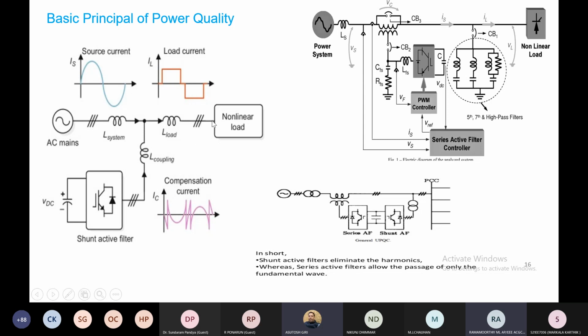Basically, all the components demanded apart from the fundamental are supplied from this side. That means if we have 1, 3, 5 components - 1 meaning fundamental, 3 meaning third harmonic, 5 meaning fifth harmonic - if 1 plus 3 plus 5 is supplied from the generator, after connection of this active filter, third and fifth will be supplied from here instead. The generator is relieved from supplying the third and fifth components, and will supply only the fundamental component to the load.